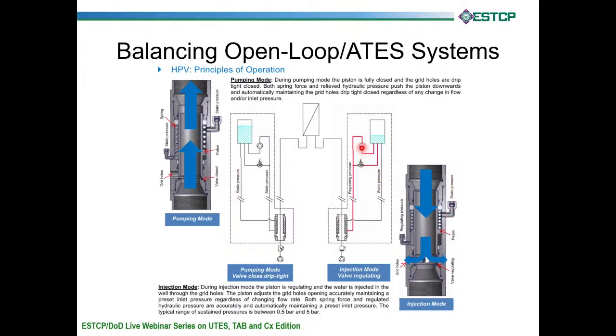Well, when we go into pumping mode, our little coffee pump turns on and applies high pressure to one side of this regulating pressure side. So high pressure comes in here. The other side is still just seeing static pressure from the reservoir, and the differential pressure presses against this seat and compresses that spring and allows this valve to open. Any other time the spring keeps the valve closed. So that's kind of how the injection valve regulates water flow to maintain the pressure set point and the maximum flow set point.